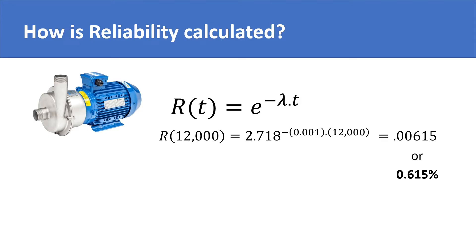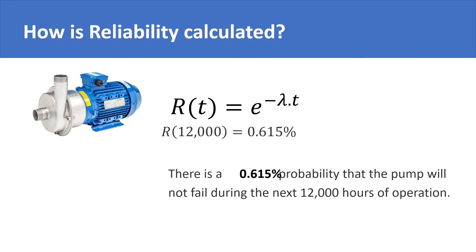So, what is its interpretation? Its interpretation is that there is a probability of 0.615% that the pump will not fail during the next 12,000 hours of operation. In simple words, the pump is bound to fail in the next 12,000 hours of operation. It is quite understandable, because remember, that the pump had a high failure rate.